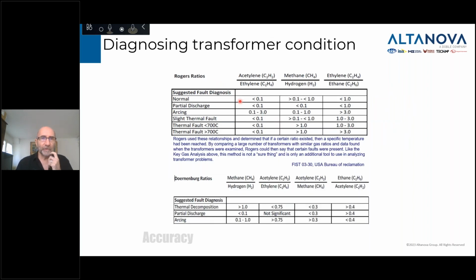The other diagnostics that have been used around the world for years are the Rogers ratio, the Dornenberg ratio, less and less, the IEC 60599 ratio, and the gas ratio. Each of them, again, was designed mostly for mineral oil. Unfortunately, to my knowledge, none of them has been updated for some of the new oils, especially the ester oils being used more and more as environmentally friendly oils. But in general, the Rogers ratio, the Duval triangle, and the IEC 60599 gas ratio are the three most used diagnostic tools around the world.